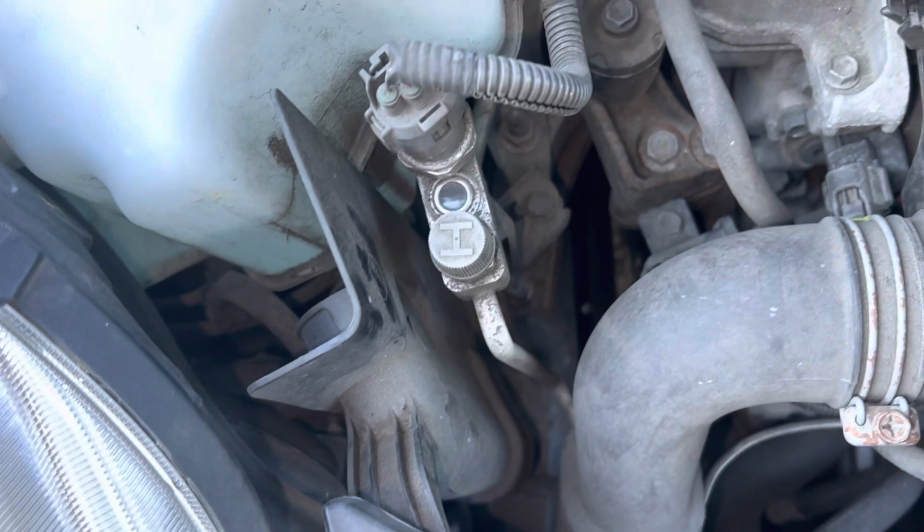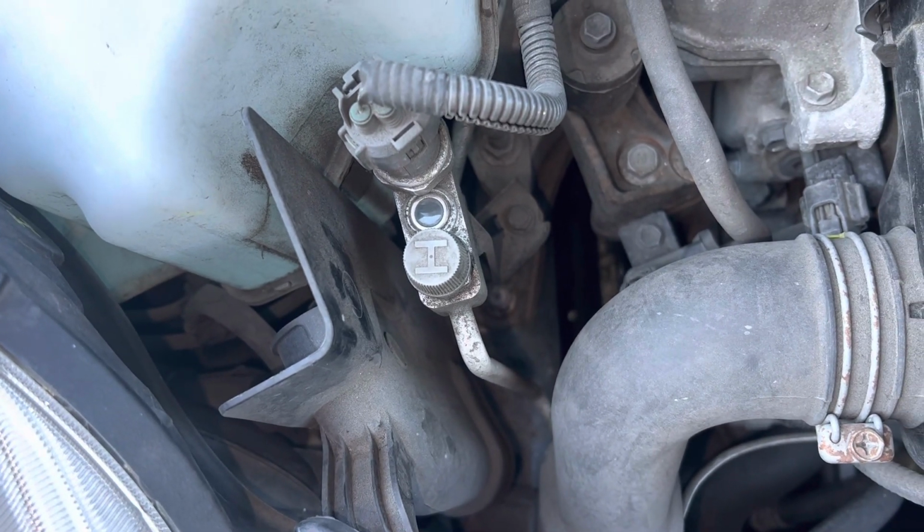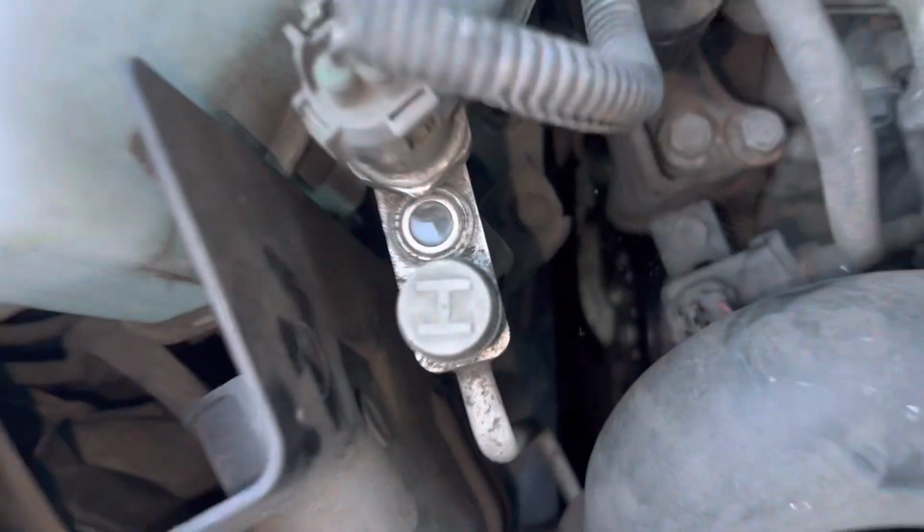That doesn't look shiny, that looks black. See that sight glass? Let's look real close. Let's get down in there. That looks like it was run low. Now if you look real carefully, I cleaned off the surface. There's nothing on the surface.